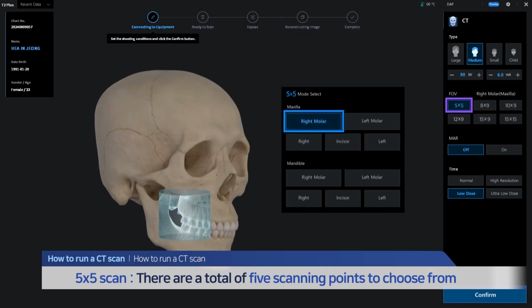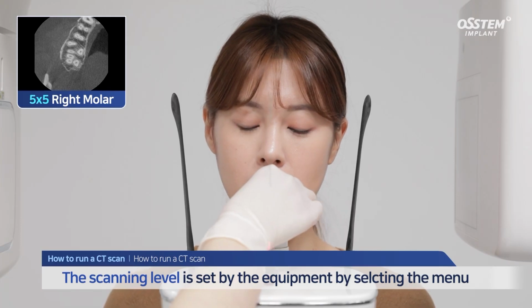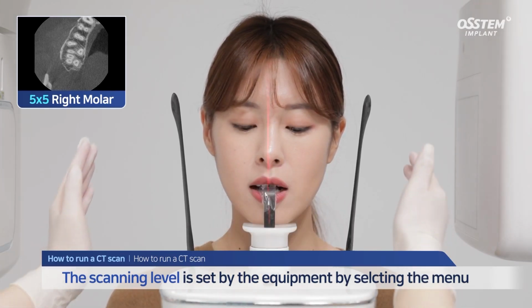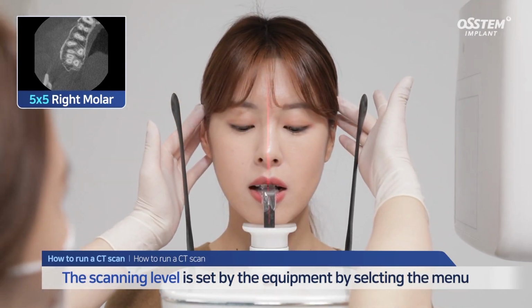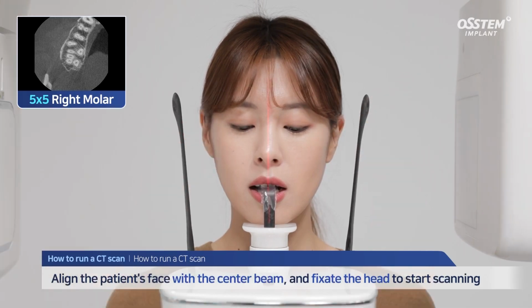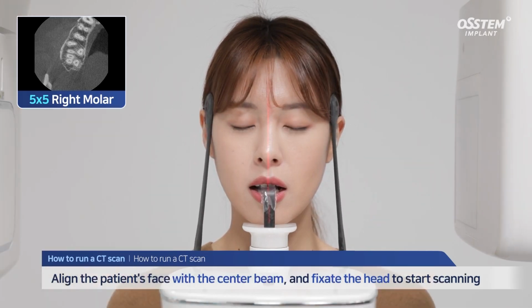With 5 by 5, you can separate the maxilla and the mandible and choose one of the 5 points for scanning. For 5 by 5, the scanning level is set by the equipment by default when selecting the menu. Align the patient's face with the center beam, then fixate the head to start scanning. Fine-tuning of the teeth position is not provided by the T2 Plus.